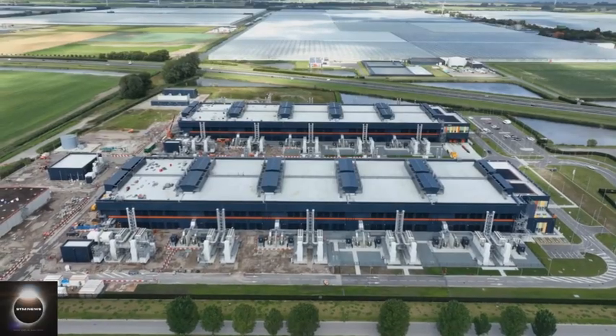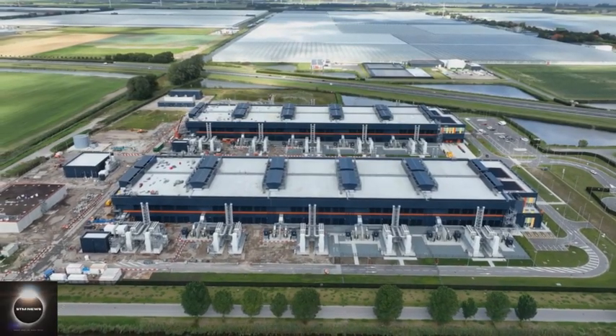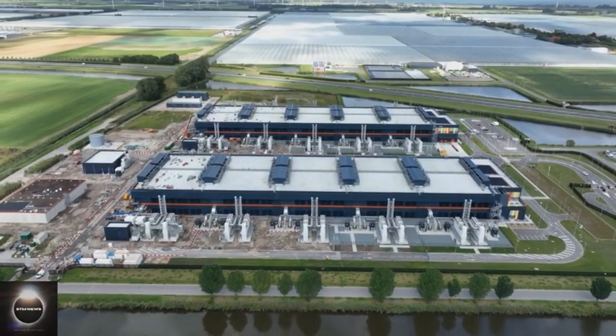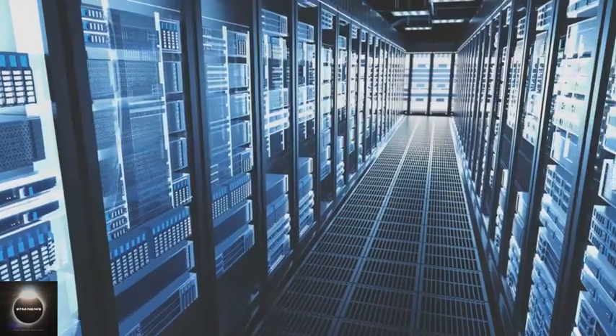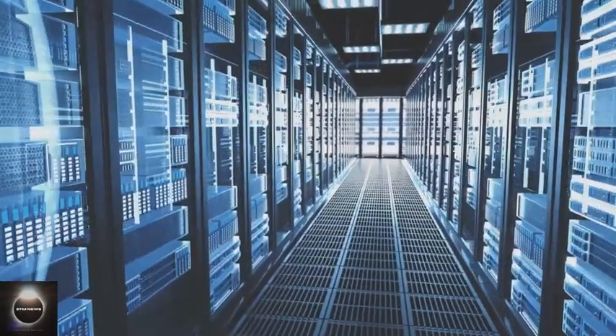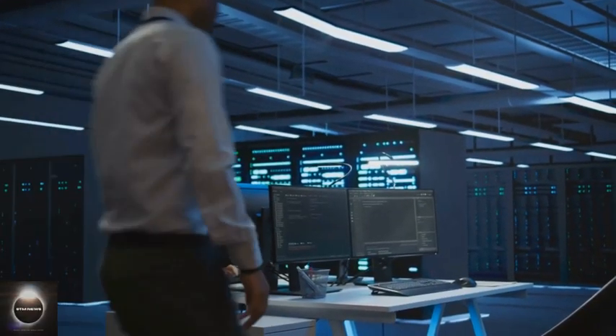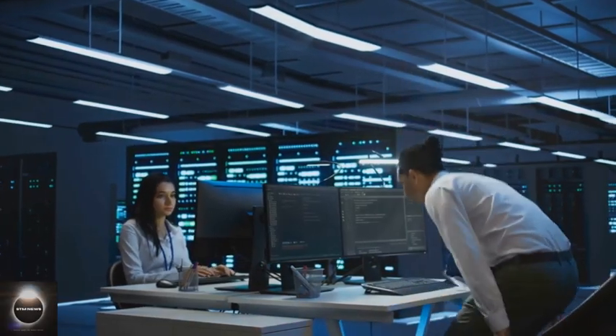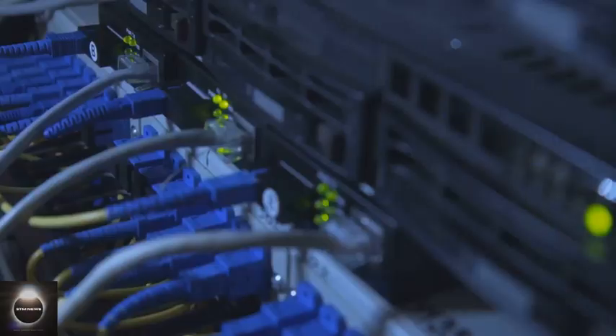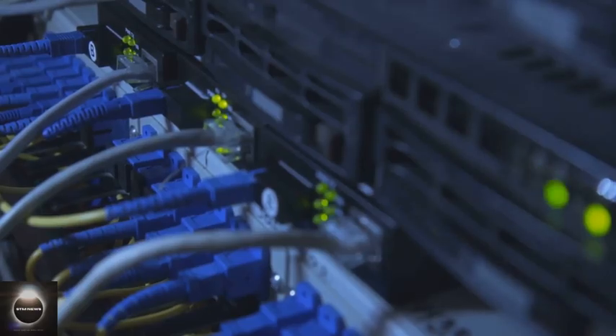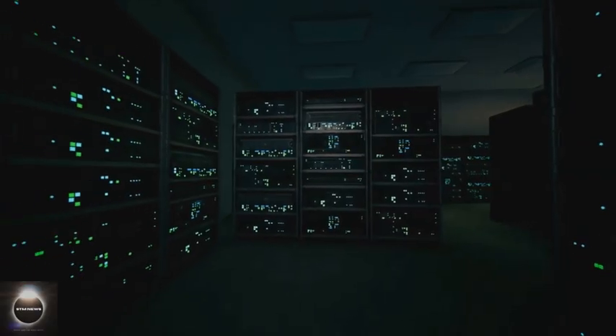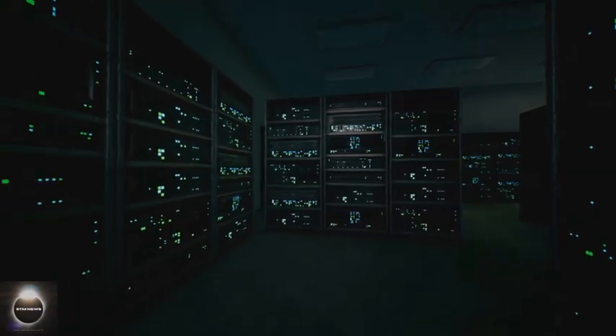As density climbs, 5 kW to 20 kW or more per rack, heat quadruples in the same footprint. That's why cooling is as critical as power. Mechanical teams size systems for peak heat, plus safety margin and future growth. They must remove heat as fast as it's produced, holding tight temperature targets. Without effective cooling, even perfect power systems are worthless.